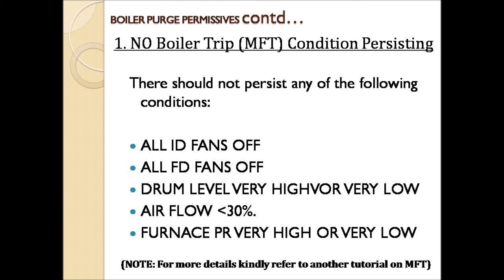The first condition among boiler purge permissives is no boiler trip condition should be persisting. Boiler trip, in other words, is MFT or Master Fuel Trip. There are certain conditions due to which MFT occurs. Among these conditions are: all ID fans off, all FD fans off, drum level high or low, air flow less than 30%, and furnace pressure high or very low. If one or more of these conditions are persisting, then MFT will be true and we cannot go ahead with boiler purging. So before going for boiler purging we have to normalize all these conditions.